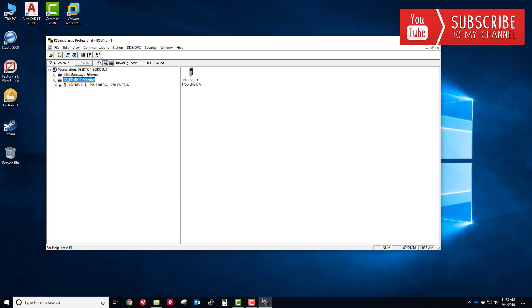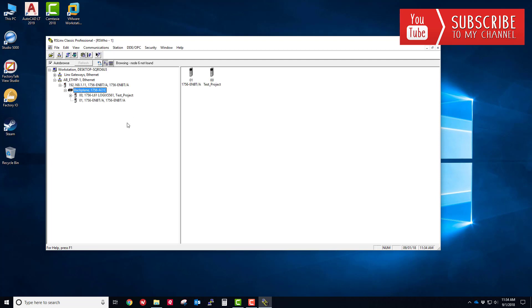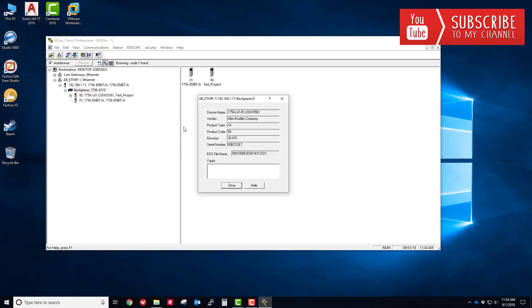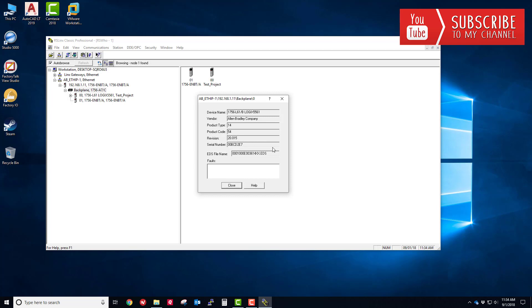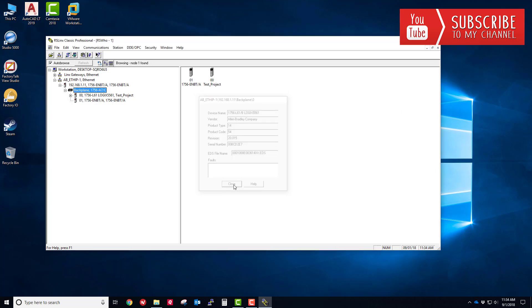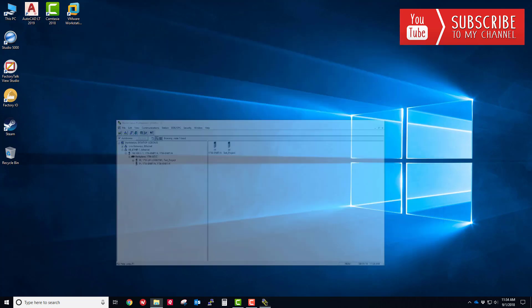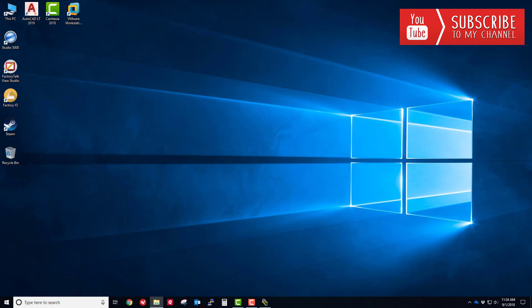Now I'm going to browse that driver. You can see right away the ethernet bridge shows up at 192.168.1.11. If I expand that, you can see the black backplane and the processor in the bridge. If I right click on the processor and go to device properties, you'll see that the revision is version 20.015. The device name is the L61, it's a revision B processor. So we know the revision of the processor is revision B and the firmware is version 20.015. We're going to go to the Rockwell website, download a lower firmware version kit, and flash that processor down to that version.